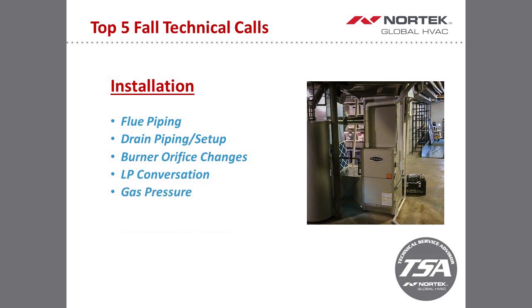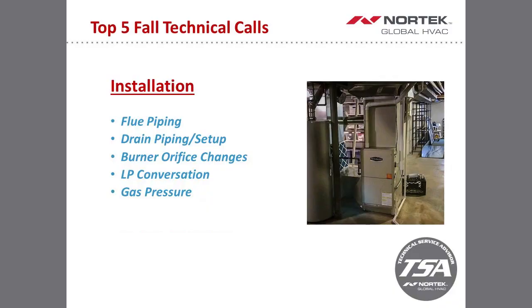Setting gas pressure, again, is a top priority, especially when you're working with LP, because you don't want to overfire the furnace because that's going to be a really bad day if that happens. Just keep in mind on high fire for LP, you need 10 inches of water column on high fire, which would also apply to single stage furnaces. And then the last thing here is the blower setup.